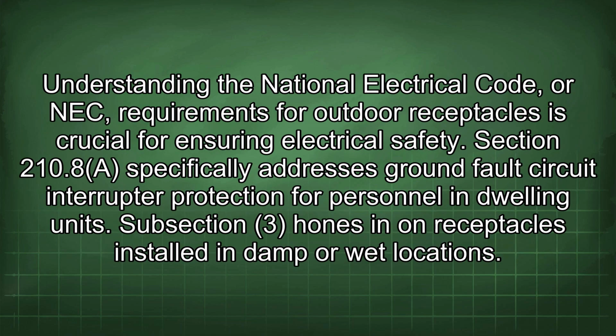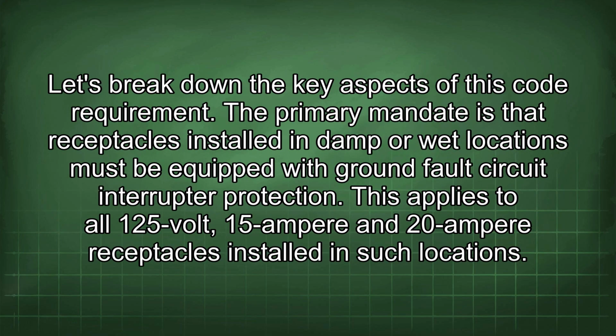Understanding the National Electrical Code, or NEC, requirements for outdoor receptacles is crucial for ensuring electrical safety. Section 210.8 specifically addresses ground fault circuit interrupter protection for personnel in dwelling units. Subsection 3 hones in on receptacles installed in damp or wet locations. Let's break down the key aspects of this code requirement.